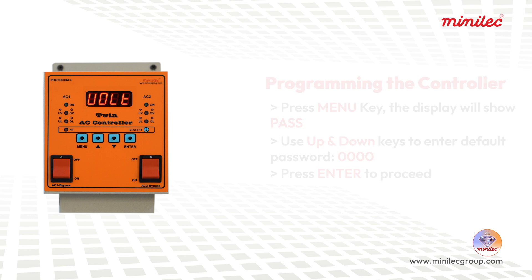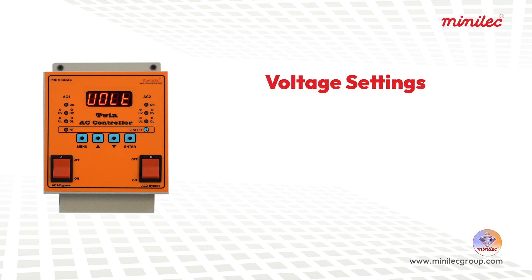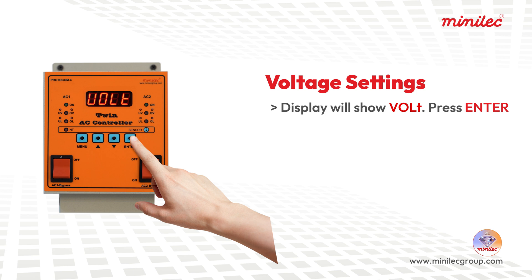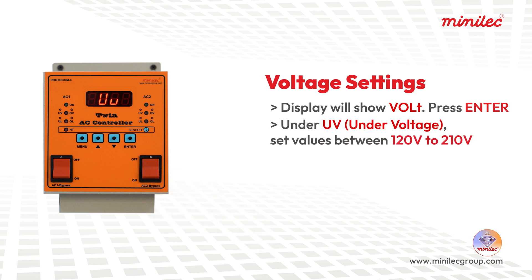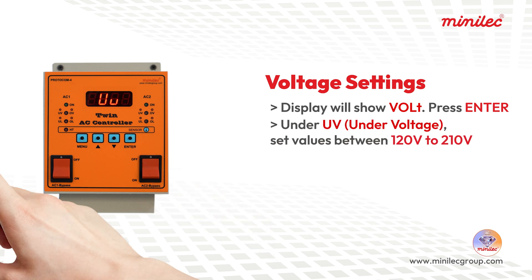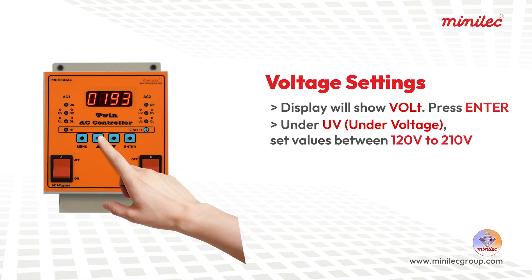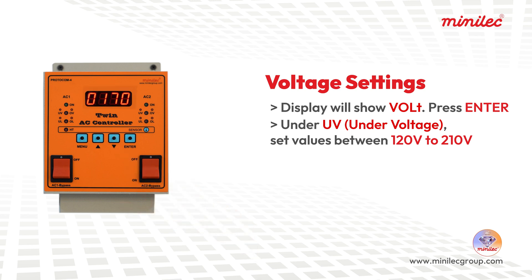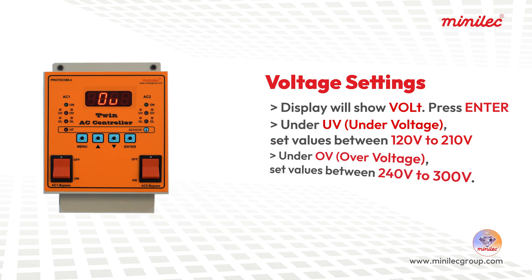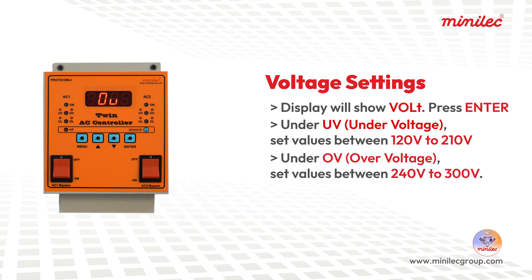Voltage settings: When the display shows VOLT, press ENTER. Under UV (under-voltage), set values between 120V to 210V. Under OV (over-voltage), set values between 240V to 300V.